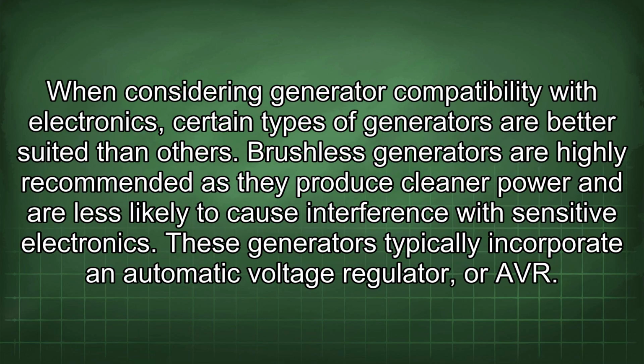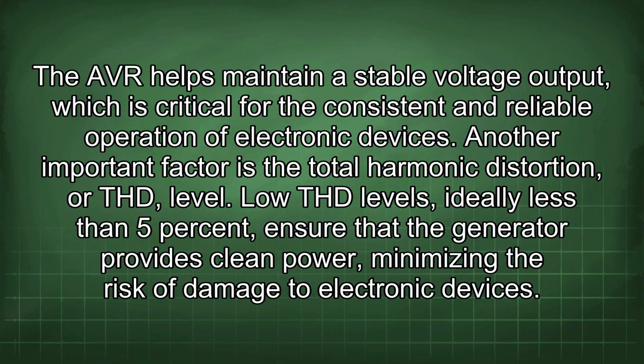When considering generator compatibility with electronics, certain types of generators are better suited than others. Brushless generators are highly recommended as they produce cleaner power and are less likely to cause interference with sensitive electronics. These generators typically incorporate an automatic voltage regulator, or AVR. The AVR helps maintain a stable voltage output, which is critical for the consistent and reliable operation of electronic devices.